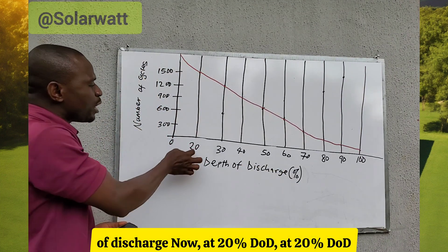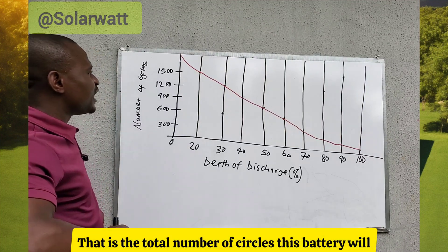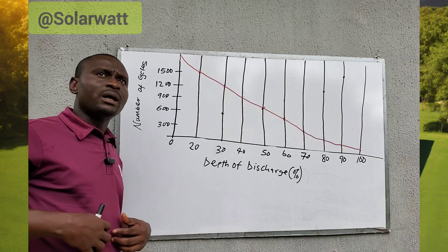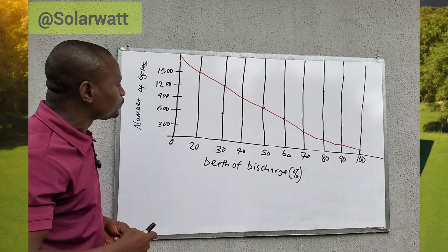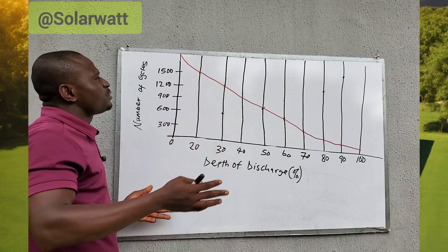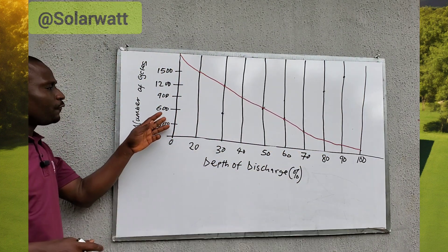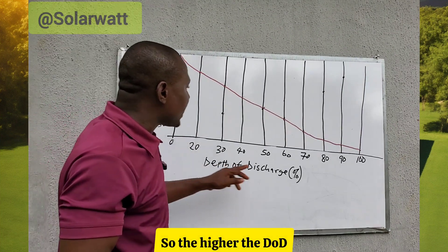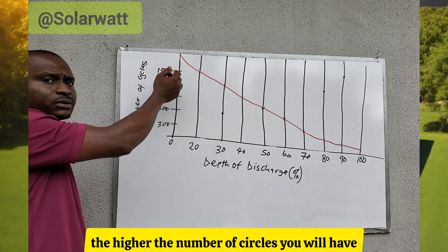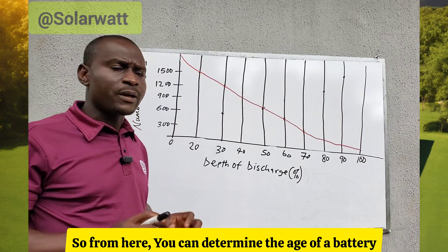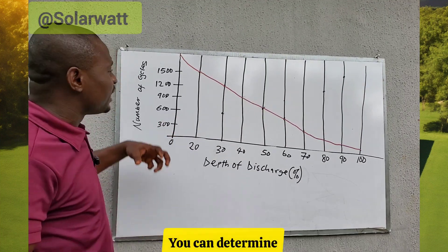At 20% DoD, you can see from the chart that the number of cycles is 1,500 — meaning this battery will give 1,500 cycles. At 30% DoD, this battery gives about 1,400 cycles. At 80% DoD, the cycles drop to about 400–450. So the higher the DoD, the fewer cycles you get, and the lower the DoD, the more cycles. From this chart you can determine the age of the battery depending on the DoD you choose.